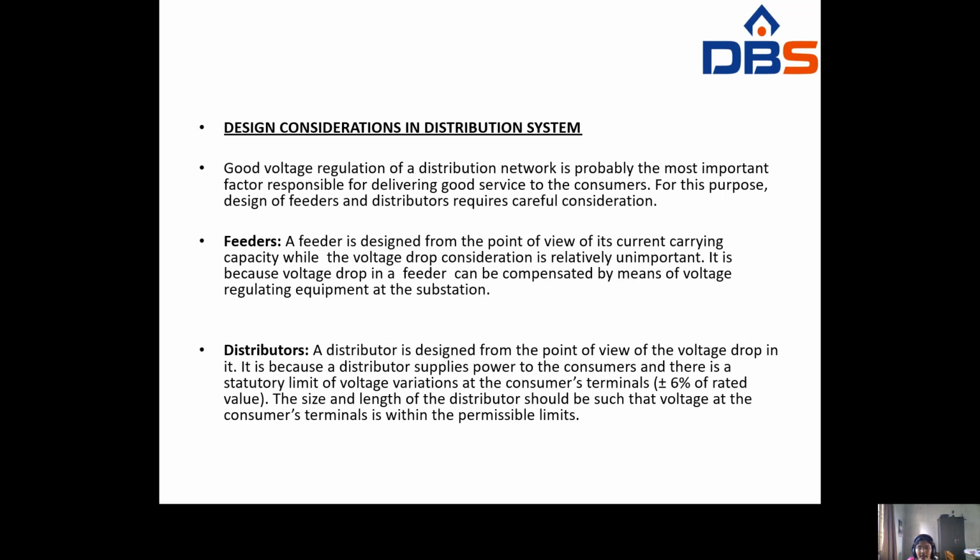A feeder is designed from the point of view of its current carrying capacity, while the voltage drop consideration is relatively unimportant. Whenever you have to design a feeder, the most important factor to take into account is the current carrying capacity, while the voltage drop consideration is unimportant. It is because voltage drop in a feeder can be compensated by means of voltage regulating equipment at the substation.